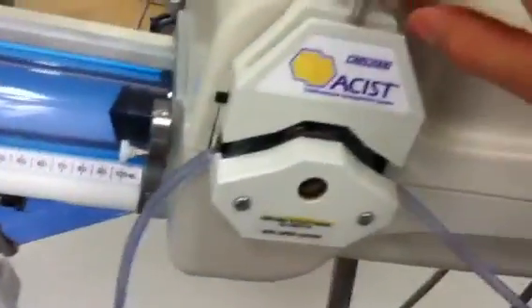So we have our system set up from the bag going through here. Inside of here are rollers that are going to force the saline through and out in the air. These here are transducers, which, as we see, should be somewhere near the phlebostatic axis. Then we have the manifold system right here. So, come over to our screen, which says load saline, all this good stuff. We go through two screens. One says purge, the next will say flush.